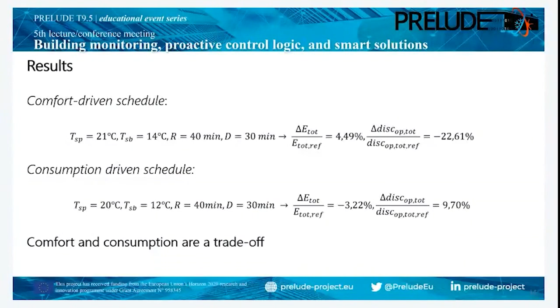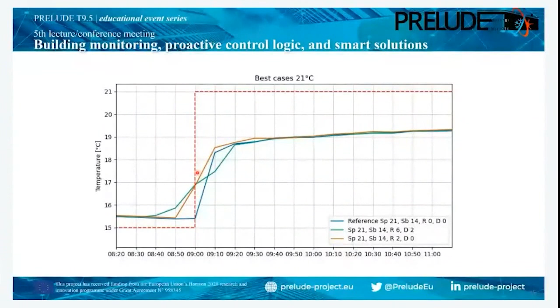But what you can do, as you can see in this slide, with a more intelligent and soft turn-on of the system, is improve this discomfort slightly. The blue line is the standard case. Once the system is on, the line goes up — this is the operative temperature. But if you preheat the building a little bit, you can keep the energy almost unchanged while having higher comfort at the beginning of the occupied period.